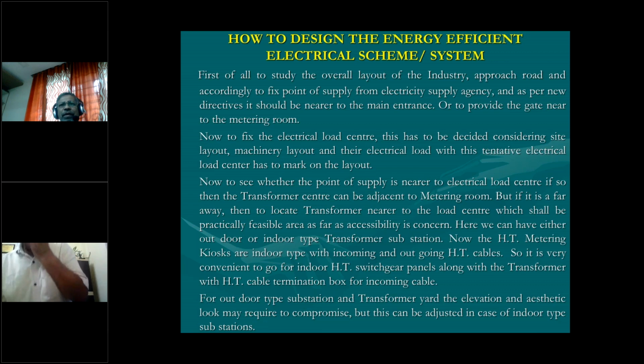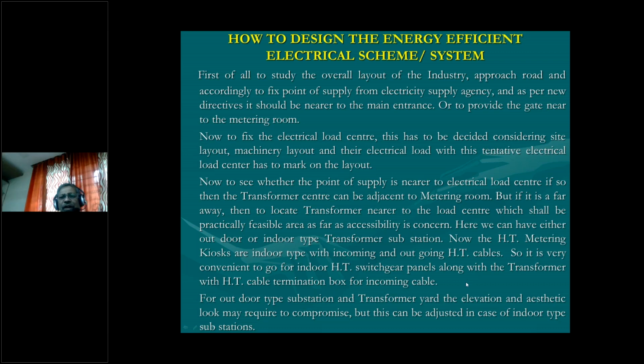But with the indoor substation, there's an indoor breaker. The total single breaker consists of CT, 3 PTs, relay panel, everything as a composite system. So you need not spend that time. Again, this is a conservation of land, so that land can be utilized for a different purpose. You can make it very compact. So that is also one of the aspects for our design.